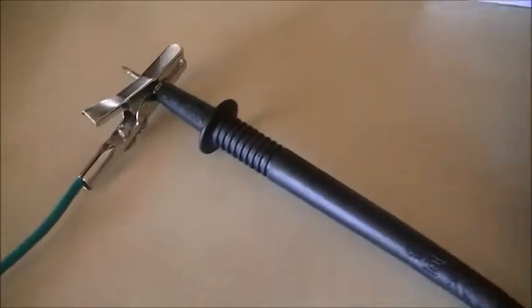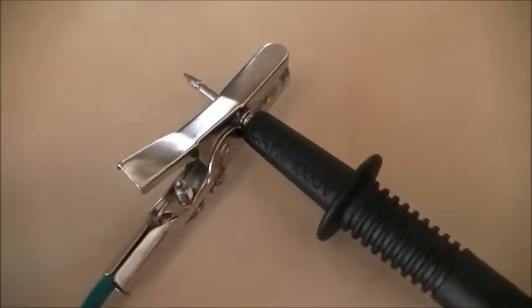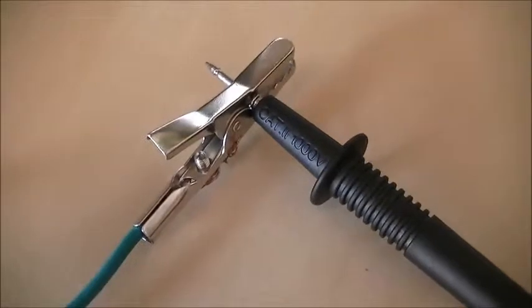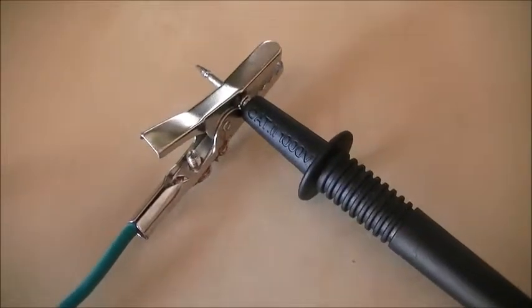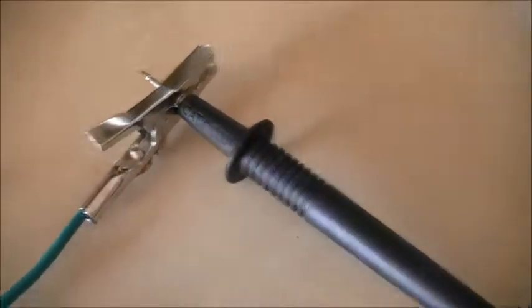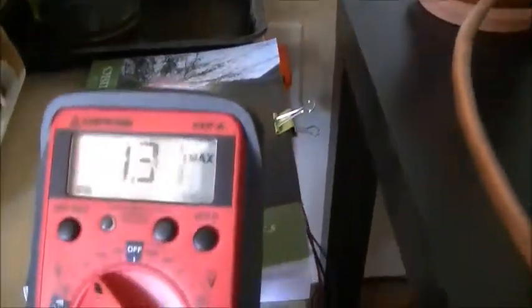I'm going to show you how we obtained that reading. The meter has two probes. The black probe goes to this connection, which goes out to an 8-foot non-electrified ground rod in my back garden. The red probe is down here, connected into the electrical grounding system, and that's what the red probe is reading from the wall outlet.